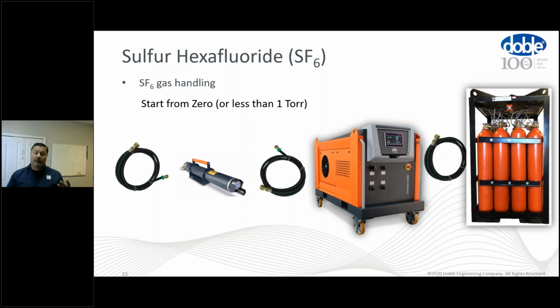Same with your hoses, your pre-filter. If you're using a pre-filter like you see here between the two hoses on the left side of the screen, that pre-filter needs to also be clean, especially if you're starting from scratch. You don't want pre-filters that have been used for a year or more than a year seeing contamination. You're just going to cross-contaminate. You're going to pass that contamination onto the gas, and the gas will not test well after recovery. You're also going to introduce contaminants into your recovery system, thus reducing the service life of it. Also, your hoses and any of the accessories that you'll be using.